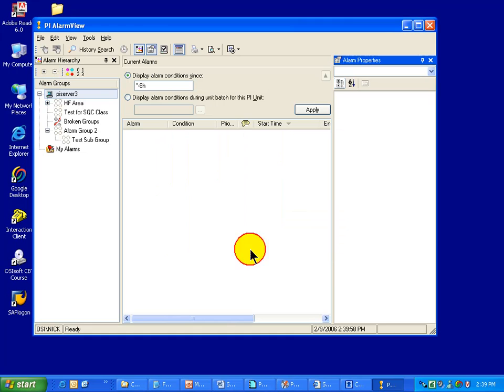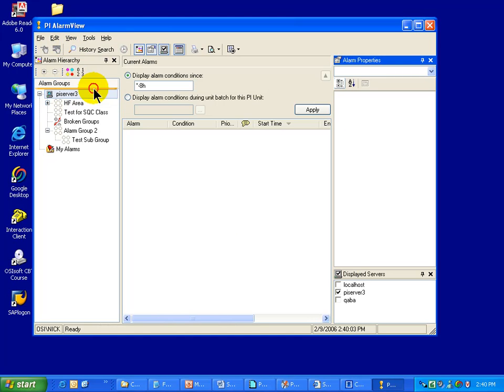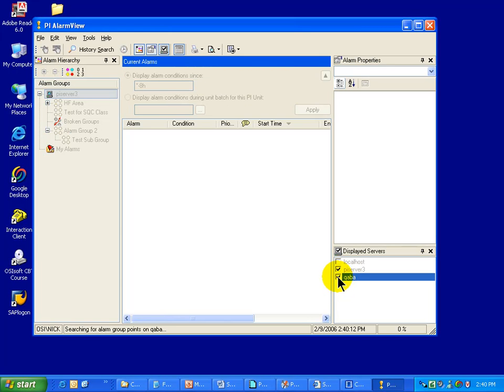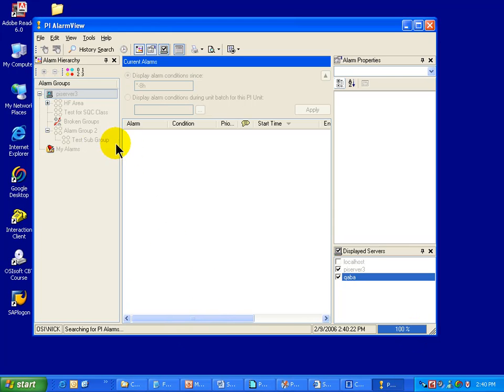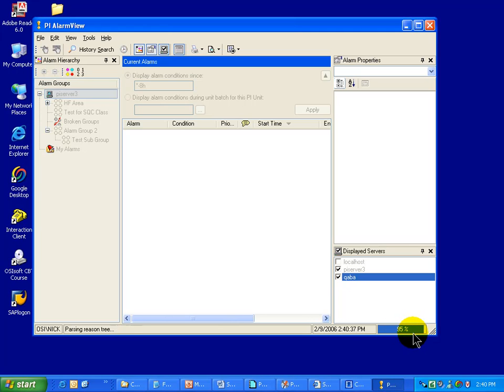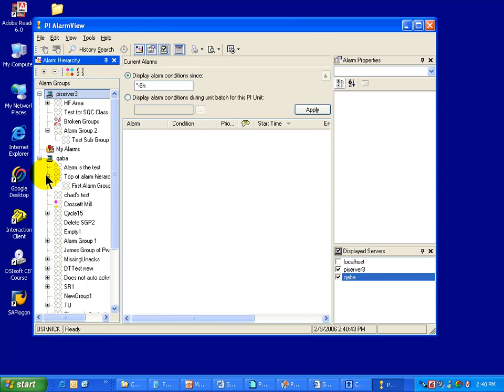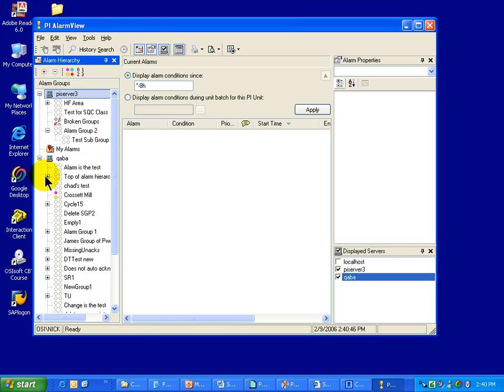I'll go ahead and connect to this server. Within the View menu, there's an option called Displayed Servers. That opens up a pane at the bottom, and I can specify that I would like this to be a displayed server as well. You'll notice that's forcing this to go out and search for alarms. This is a fairly involved server, so there's going to be a lot of alarms — it's going to take a little time. When finished, I should see a brand new server listed here and be able to drill down through its hierarchy. Here we can see the progress bar parsing out all the alarms, and here are the results — so I can now manage multiple PI Servers right here.